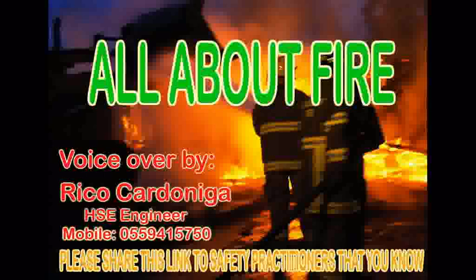Special dry powder extinguishers are required to extinguish these fires, which may contain powdered graphite or talc. Class F, fires which involve high temperature cooking oils or fats in large catering establishments or restaurants. Electrical fires, fires involving electrical equipment or circuitry. Extinguishers specifically designed for electrical use, like carbon dioxide or dry powder.